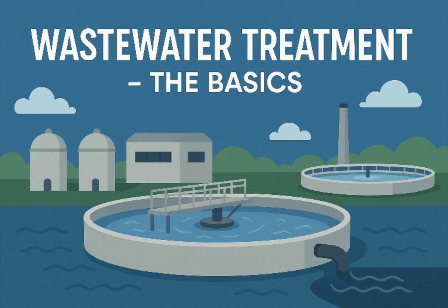Okay, let's circle back. All that sludge settled out in primary and secondary. What happens to it? You can't just landfill all of it, can you? Good question. No, that sludge needs treatment too. It's full of organic matter and bacteria. A very common method is anaerobic digestion. Anaerobic, meaning without oxygen. Exactly. Specialized bacteria that thrive without oxygen break down the sludge. This usually happens in large heated tanks, maybe around 38 degrees Celsius, for about 10 to 20 days.